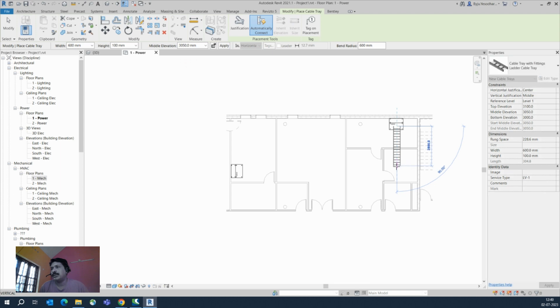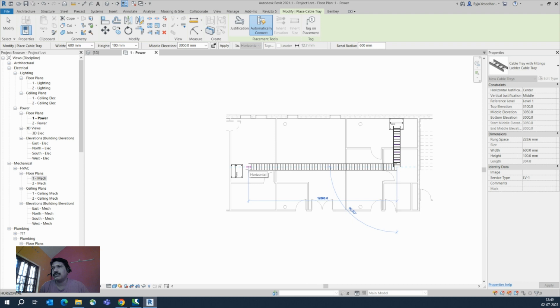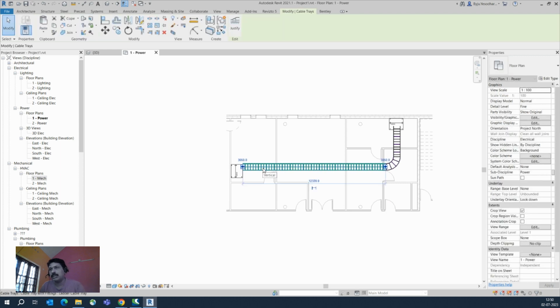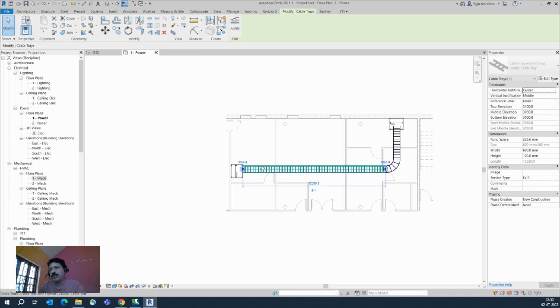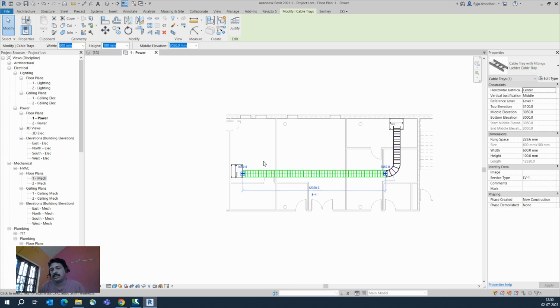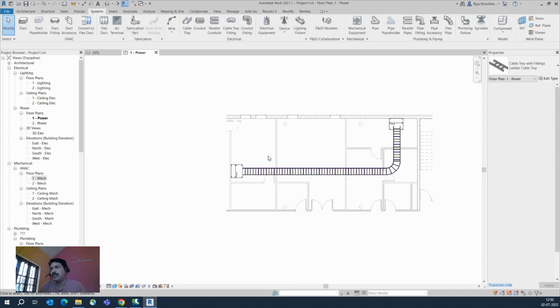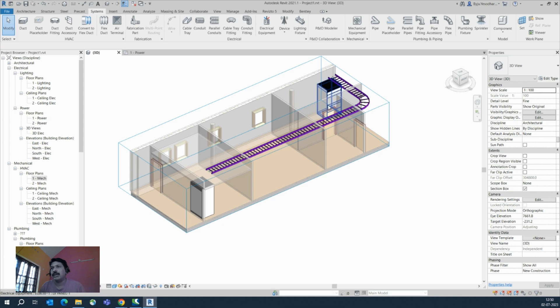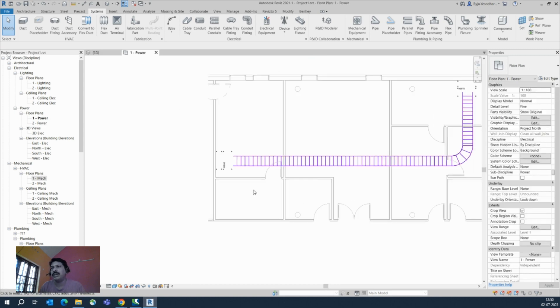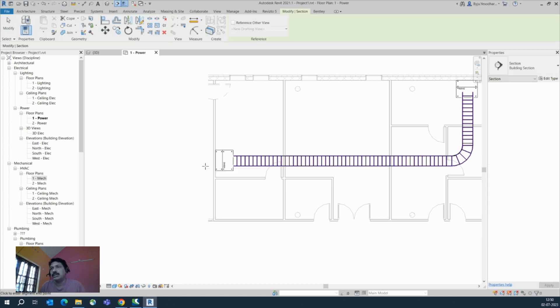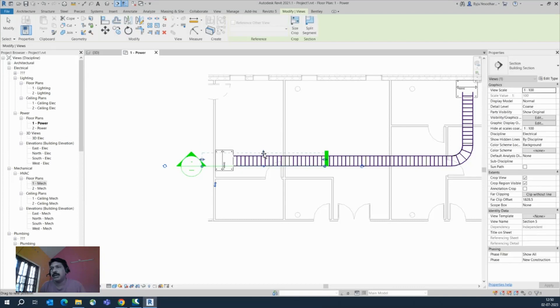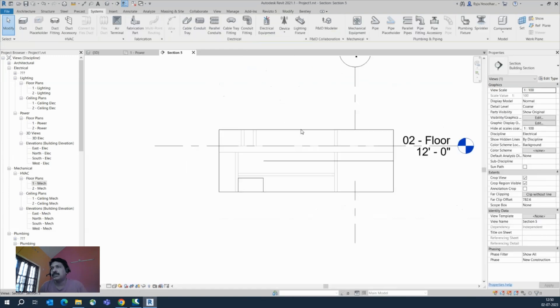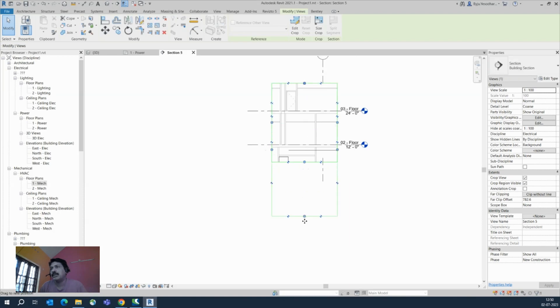I'll start drawing one cable tray and connect it to the panel. I'll drop it here and adjust using the keyboard arrow keys to position the cable tray where needed. In the 3D view you can see the cable tray running from one panel to another. To drop the cable tray down, go to a section view — right-click and create a section close to the cable tray and panel.